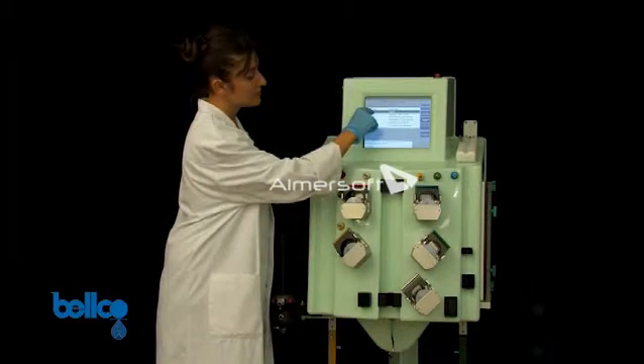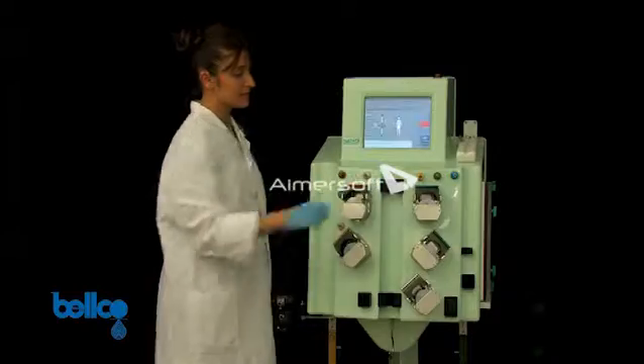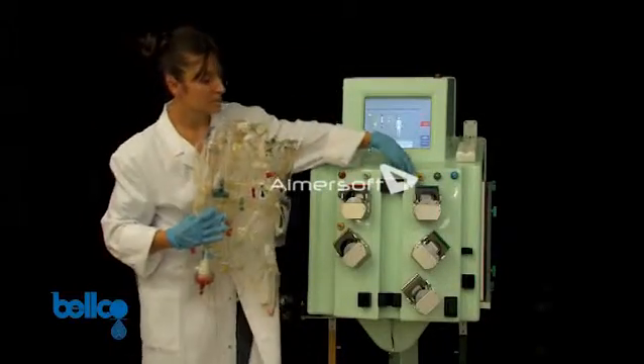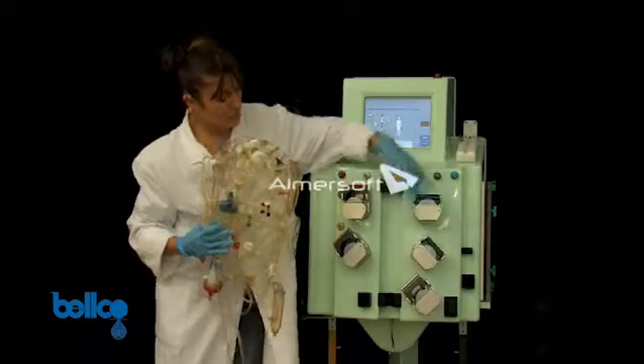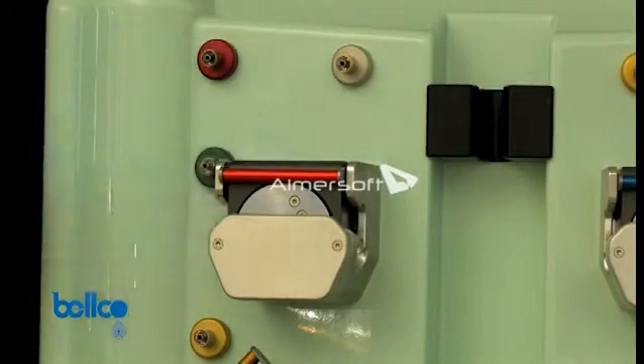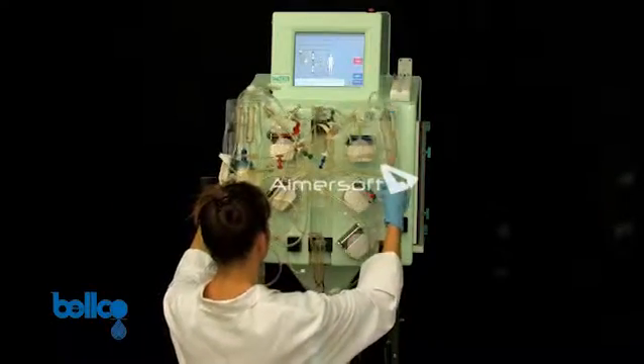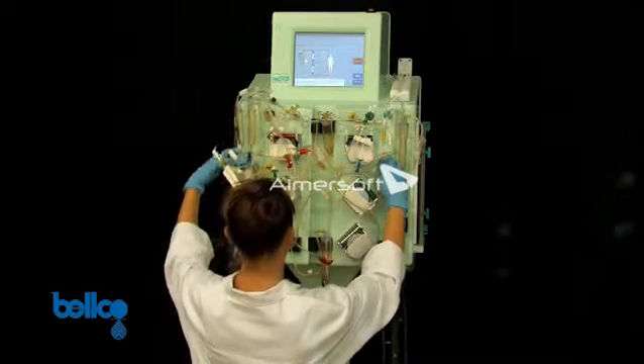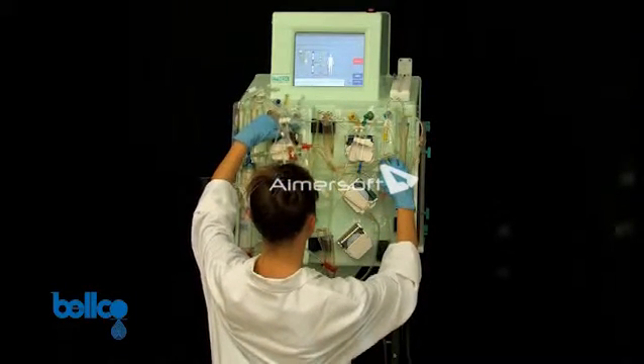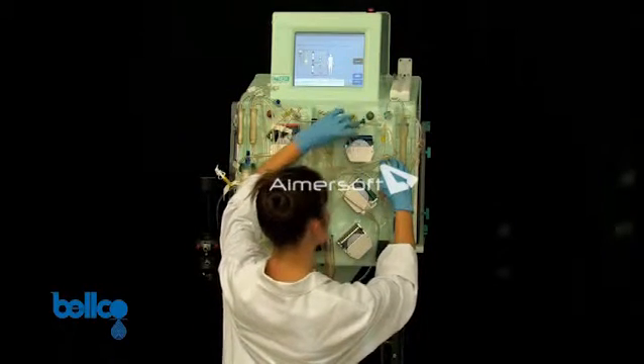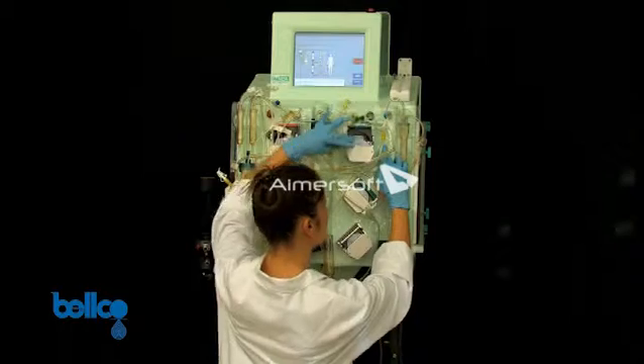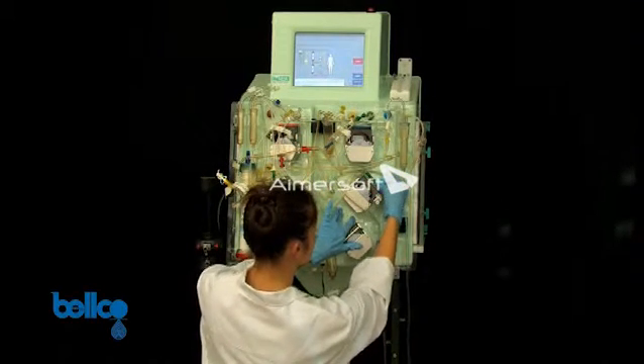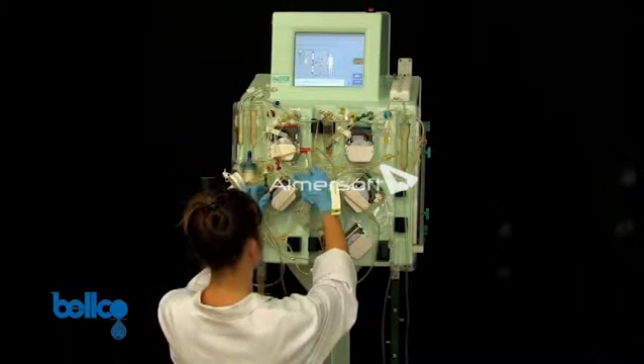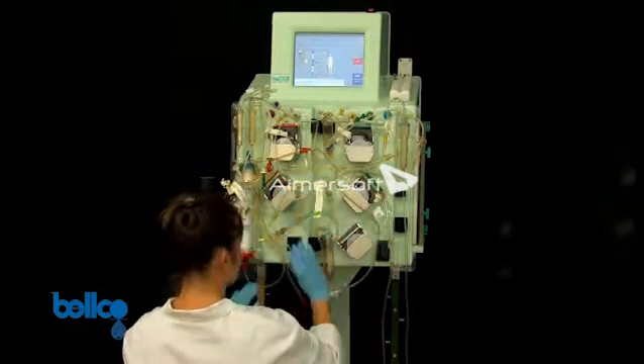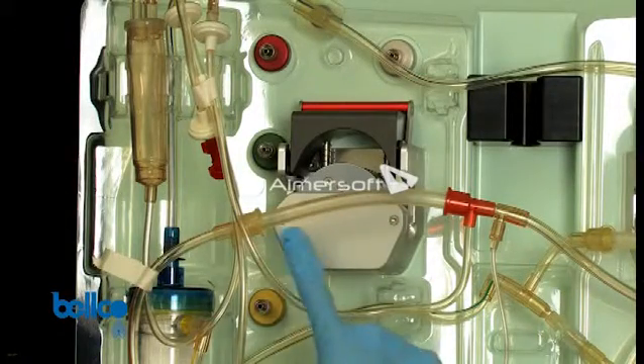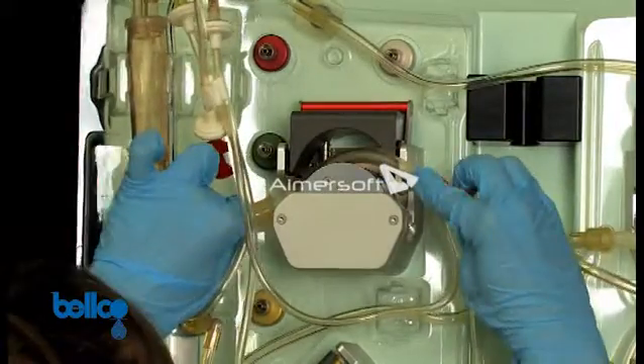Use the touch screen to select the desired Cpfa treatment. Take the single-use device and check that all 5 pump covers are closed. Open the single-use device and position the set on the machine as shown. After positioning the set on the machine, fasten it by opening the pump covers. Fit the pump segments of each single pump as shown.